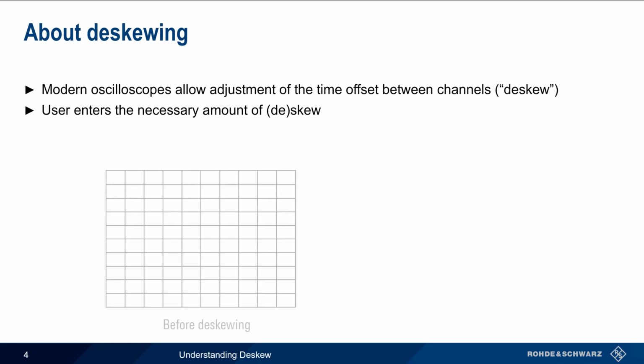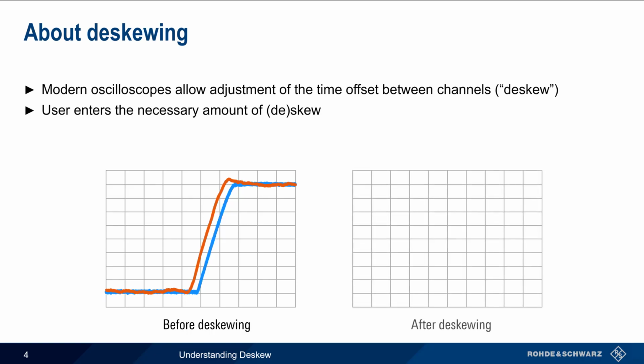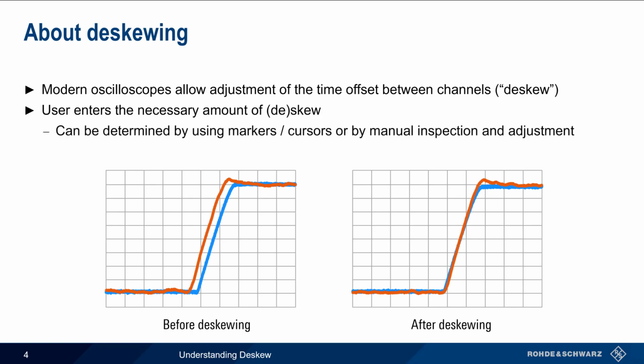For example, the two channels shown here do not overlap due to skew between the channels. After entering the appropriate amount of skew, the channel waveforms now overlap, meaning that the signals have been de-skewed. The necessary amount of de-skew can be determined either by placing markers or cursors on the waveforms and measuring the time difference, or by manually increasing or decreasing the amount of skew while visually inspecting the waveforms.